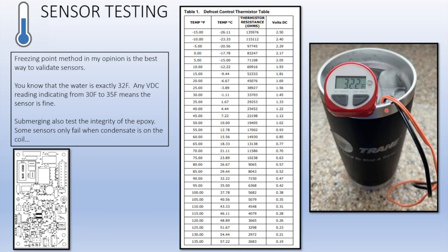So you're doing two things. You have a calibrated testing media that you've put them in that you know is 32 Fahrenheit. The other thing you're doing is you're submerging those sensors, which verifies the integrity of the epoxy in that sensor. Because sometimes we see sensors where they test out just fine, and then when the coil starts condensing and has some liquid on it, that liquid gets into the sensor and the sensor fails. And when you're there, the sensor is dried out again and it looks like it's just fine. So just submerge it in water, make it ice water so that you know it's 32 Fahrenheit. And as long as it's between the numbers for 30 and 35 Fahrenheit, you're good.